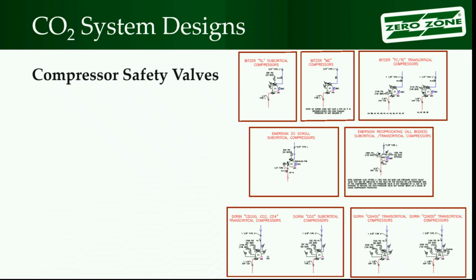Another thing to be aware of: a lot of the systems we have out there, and I've seen that with competitor systems as well, the safety valves, when you look at them, do not have an NPT thread on them, the valves used by the compressor folks. So typically they are not piped to the outside. They usually have deflectors built right into the valve, so if that valve would release, it won't spray at you, it'll spray at the compressor, then it'll fan out over it. So something to be aware of, where your body is in position and what you're working on, right?